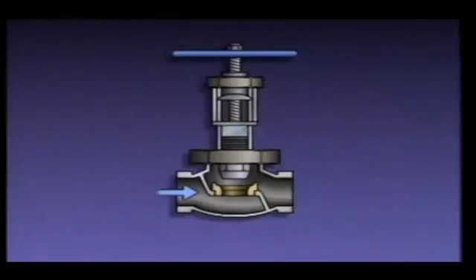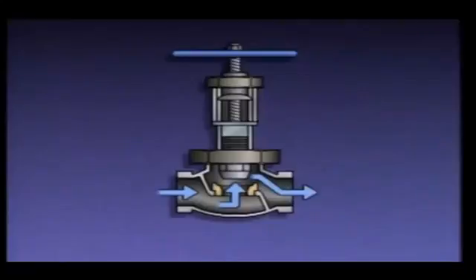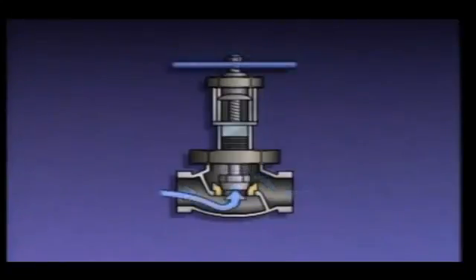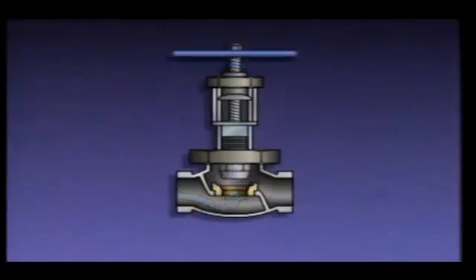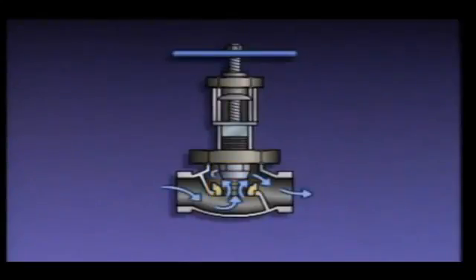Fluid flow enters a globe valve here and exits here, making several right-angled turns as it passes through the valve. Globe valves are normally arranged in a piping system so that the higher pressure side is acting under the disc of the valve. This makes it easier for an operator to open the valve. As a globe valve is opened, the entire disc and seat are exposed to the fluid flow, which prevents uneven wear of the seat and disc.